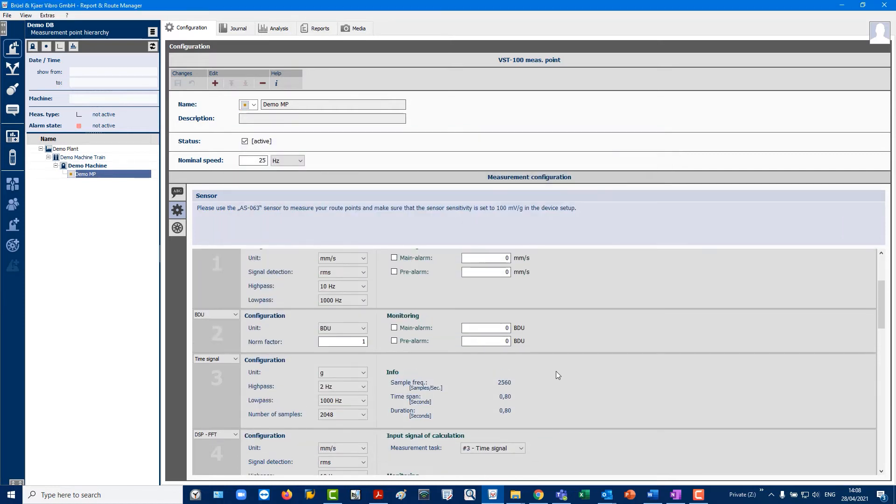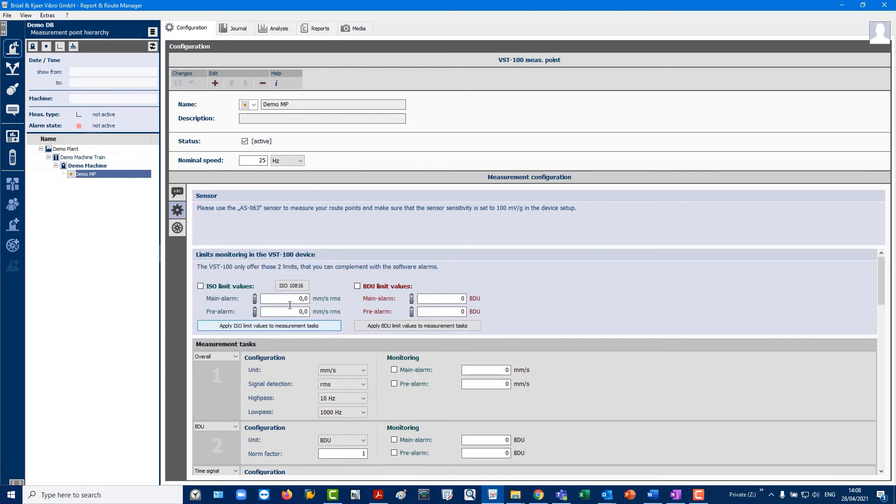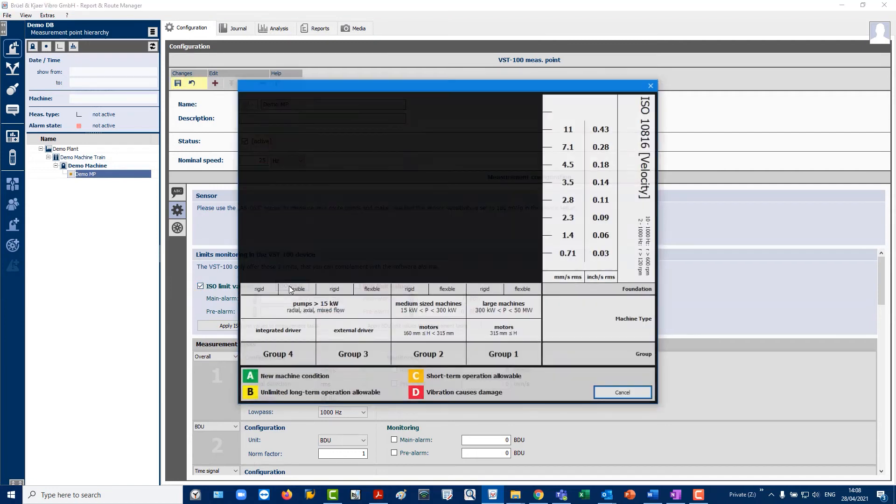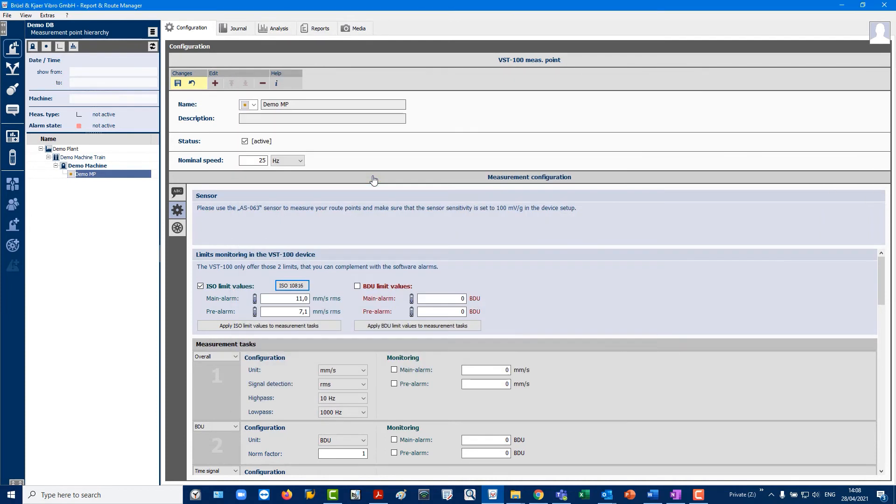Note the foolproof interactive GUI table for assigning alarm limits according to ISO 10816 for classified machine types. For example, a pump with more than 15 kW. Apply the ISO 10816 alarms by clicking on Apply ISO limits.